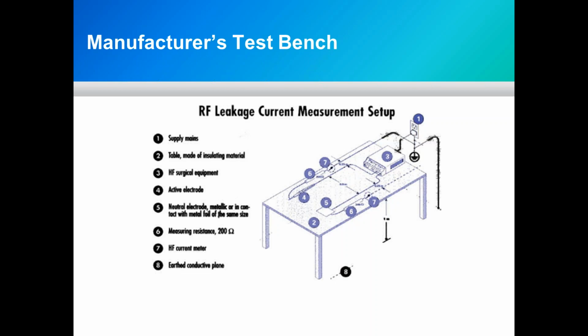It's interesting, when I do these presentations live at a trade show or a biomed show, during the high frequency leakage portion of the discussion, I always do an active demonstration where I take that long pencil cord, coil it up, press it on top of either the generator or on top of the analyzer, and rather than seeing 73 milliamps of leakage current, I can get up to 450 milliamps of leakage current by adding inductance and capacitance. So very, very important. Something to keep in mind if you have a test that's failing. Take a look at your leads, make sure everything's laid out, pretty short as possible, and a good opportunity to save that generator, pass the test, without going to the famous wooden table.